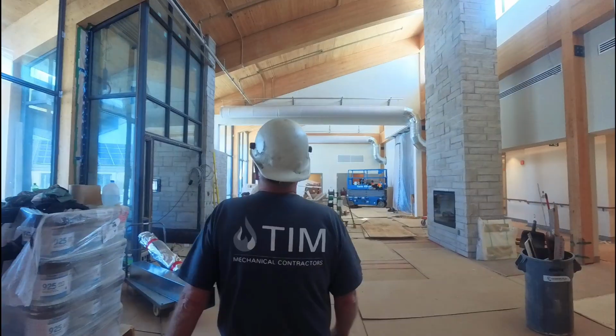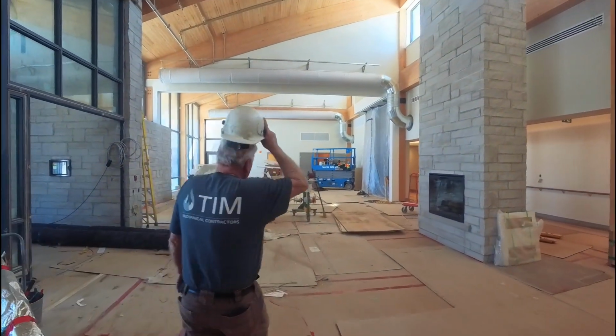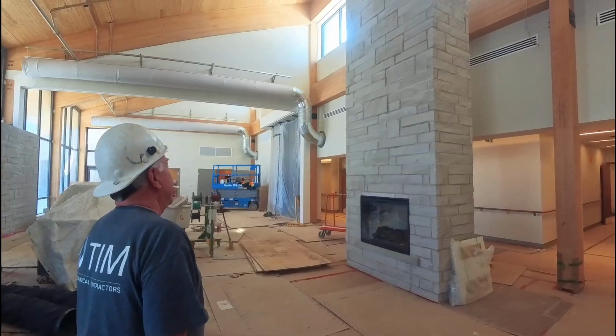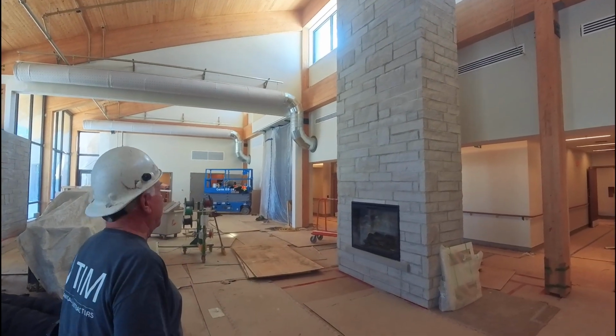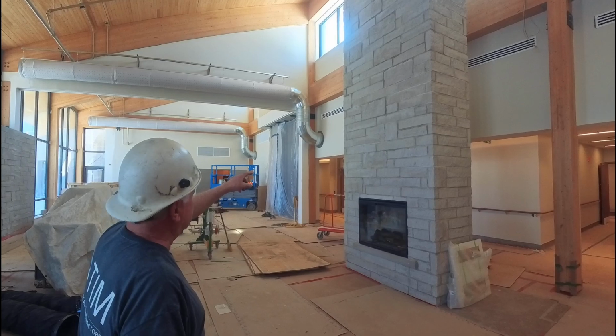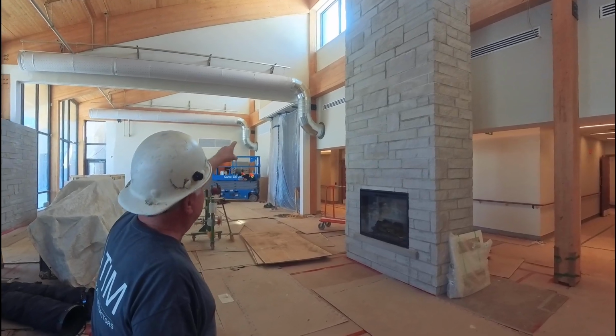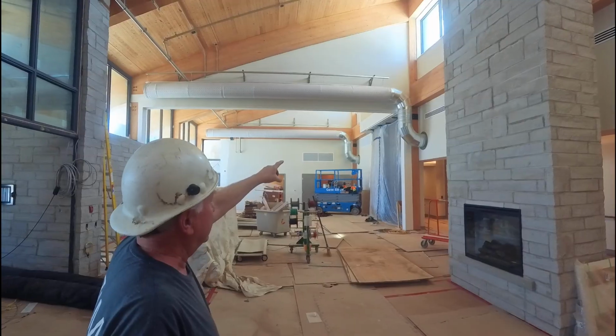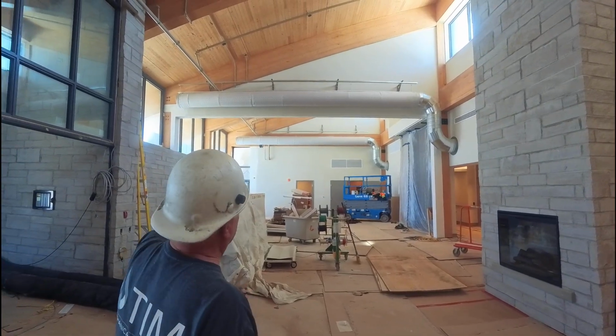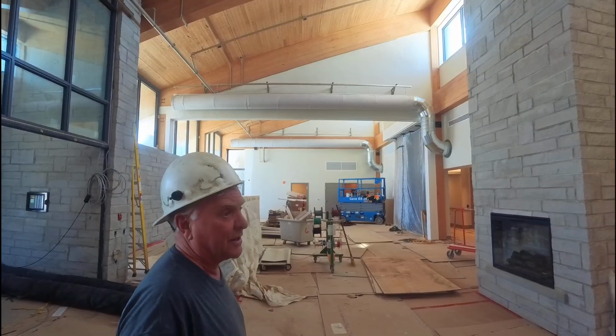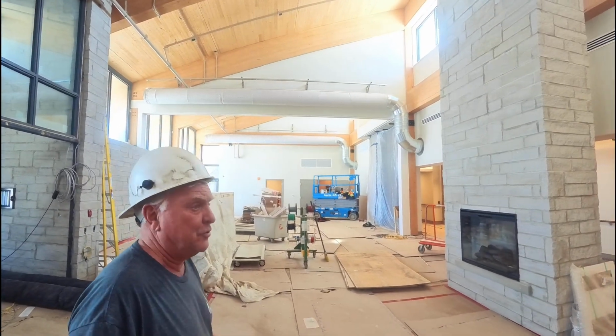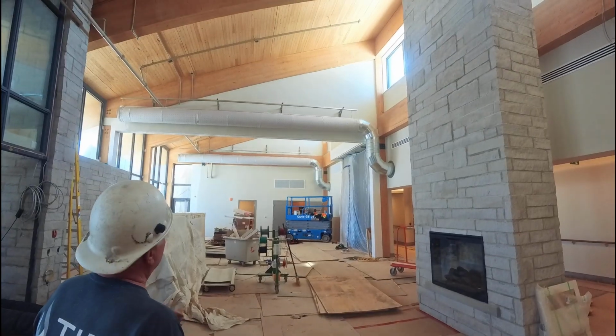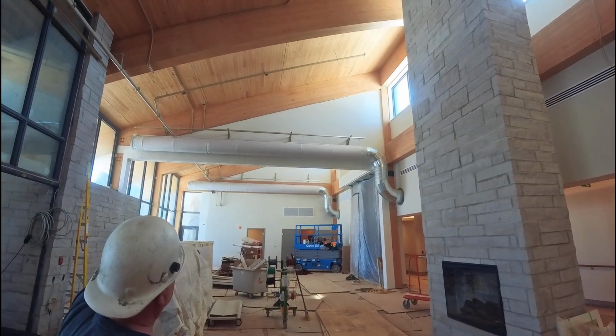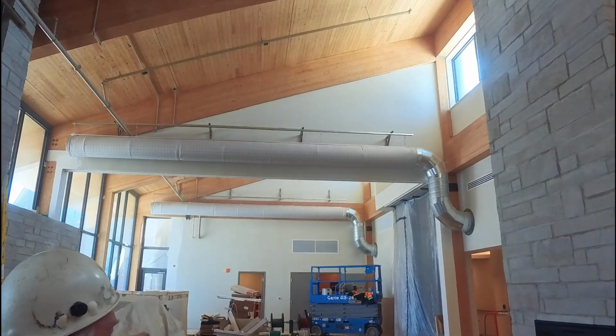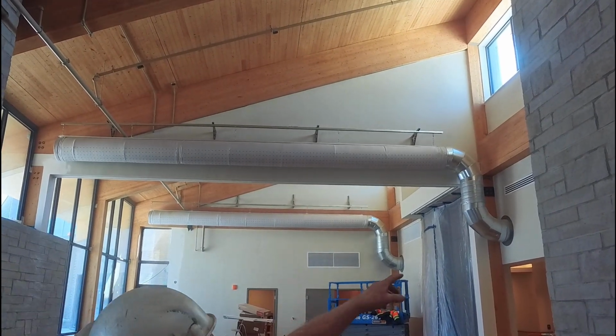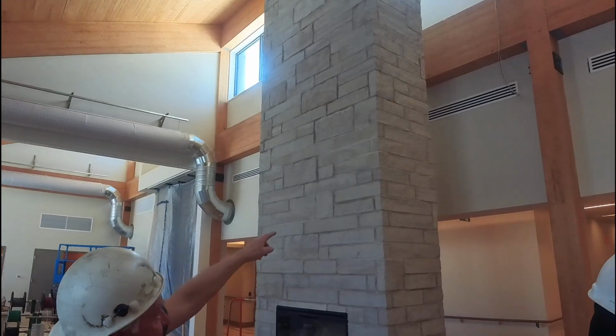This room here is the main entrance of the building, and air handler number 2 is looking after this big room. It has two large VAVs with 12-inch necks, turning into that 18-inch round ductwork, and then turning into that 18-inch round fabric duct, or sock duct, or fabric diffuser. It's full of air right now as the unit's running, and all that series of small holes is supplying air for this entire area.